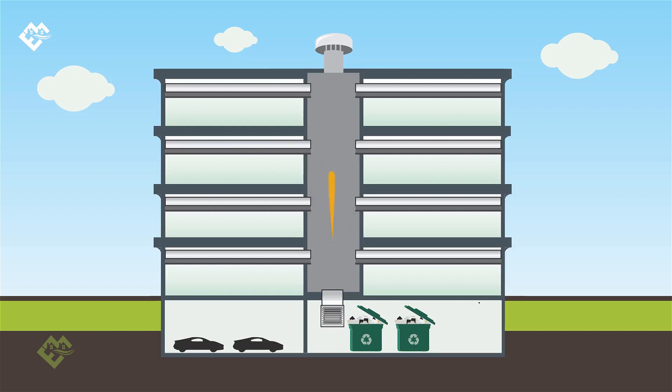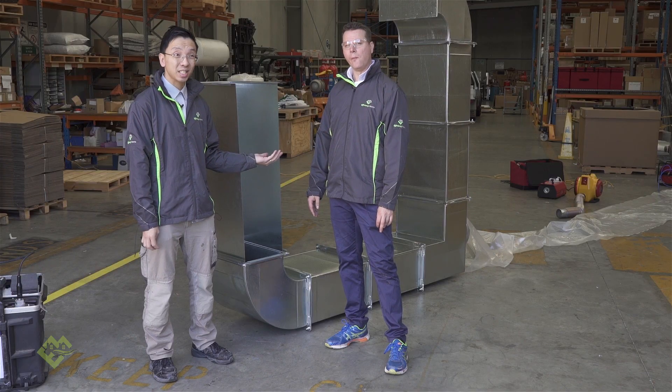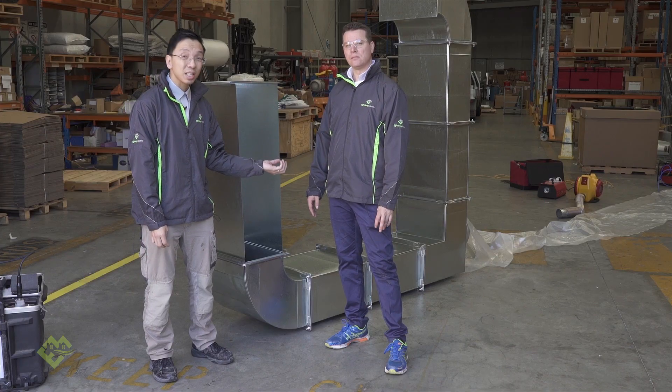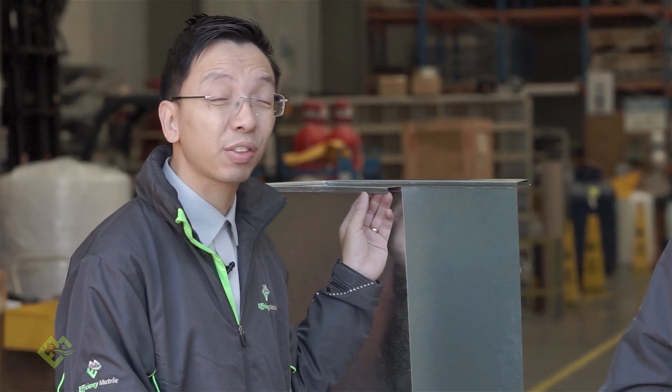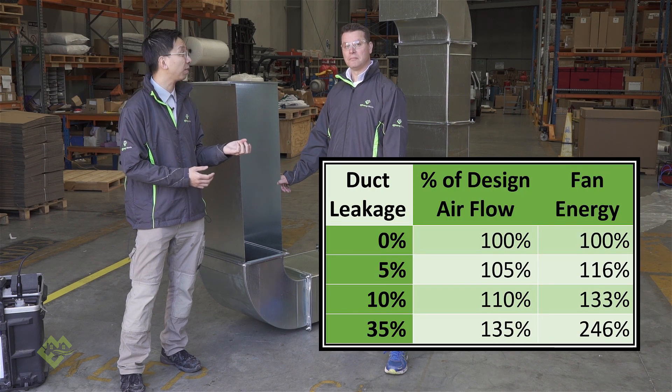What does it mean to have a percentage of leakage in ductwork? Leakage in ductwork is not as straightforward as other forms of wastage because the energy requirement for generating airflow follows a cube rule. A 5% increase in airflow translates to a 16% increase in fan energy, and a 10% increase results in a 33% increase. In some of the worst cases, if your ductwork is leaking at 35%, you are using an extra 146% of energy on top of the original design energy — a huge implication in terms of fan energy requirement.